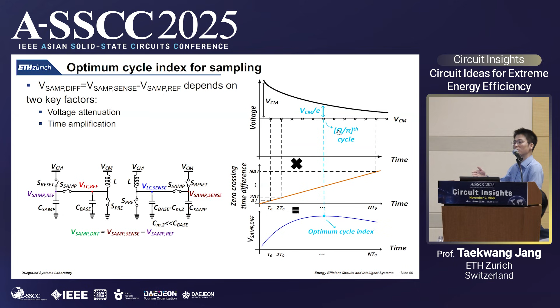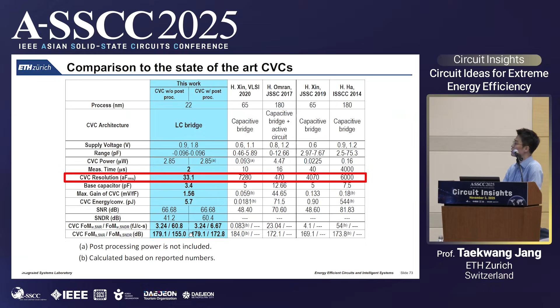So these arrows are sampled voltages. And it shows a very simple and cute formula: Q factor divided by pi cycles is the ideal sampling point. So let's say Q is about 40, then you want to sample about 10 cycles later, right? In doing so, we achieve a CVC resolution of about 33 attofarad, which is very good compared to prior work, and have a very good SNR and SNDR overall. So this resonant LC bridge can also be a very effective technique.